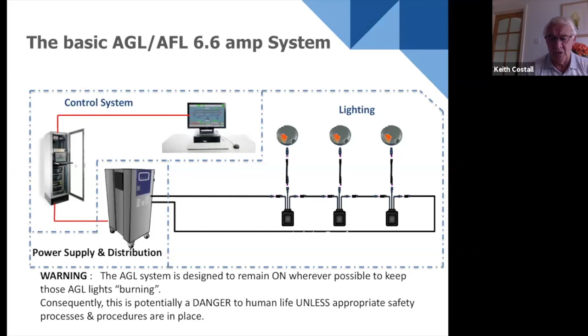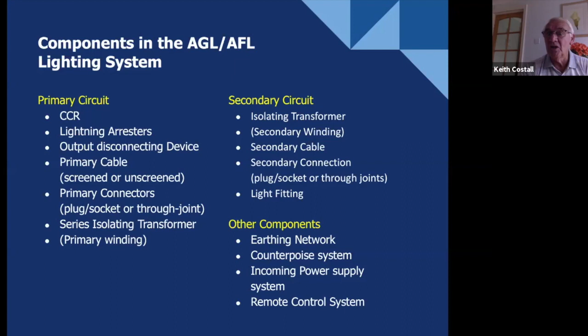The voltages could be up to 4,545 volts, maximum at 6.6 amps. Remember, voltage burns, current kills. The secondary circuit is the low voltage side, but if we have an electrical short between the primary and secondary, the voltage on the secondary rises to that of the primary circuit. Therefore, we also have additional components such as earthing networks, or a counterpoise earthing network, which is for lightning protection.